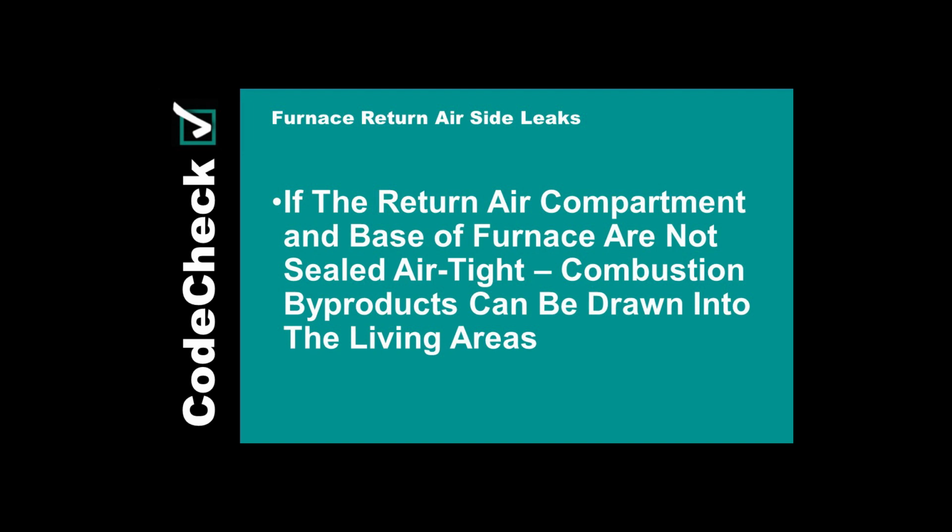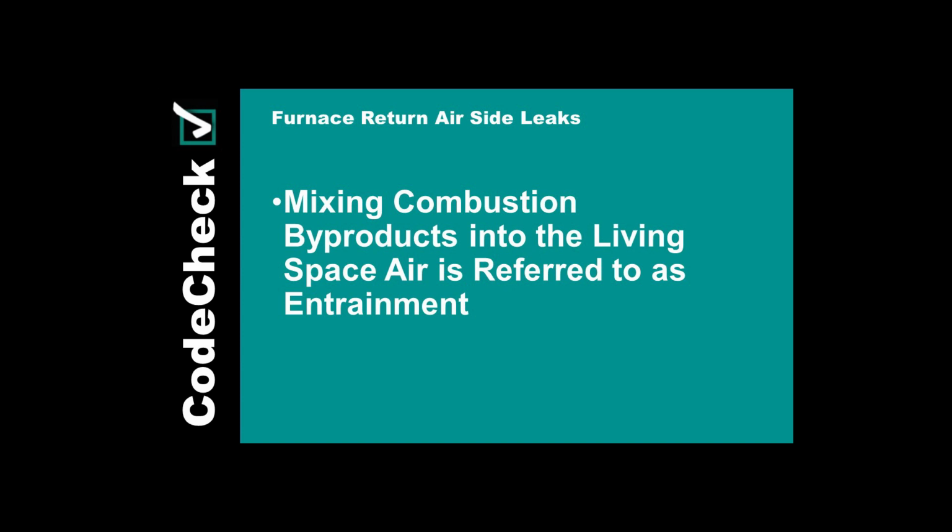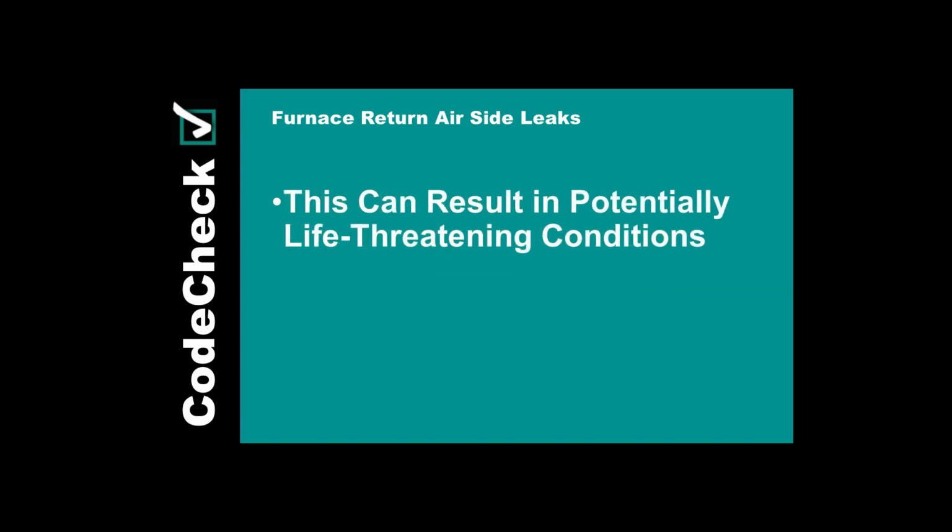If the base of the furnace isn't sealed properly where it connects to the return air, or there's leakage in the return air plenum, this can result in byproducts of combustion being drawn into the circulated air for the living space. Mixing return air, cold air from the dwelling, with combustion byproducts is referred to as entrainment, which is simply a fancy word to mean it gets mixed. Entraining combustion byproducts into the air circulated in the living space does pose a significant safety concern, and in really extreme cases can actually be life-threatening.